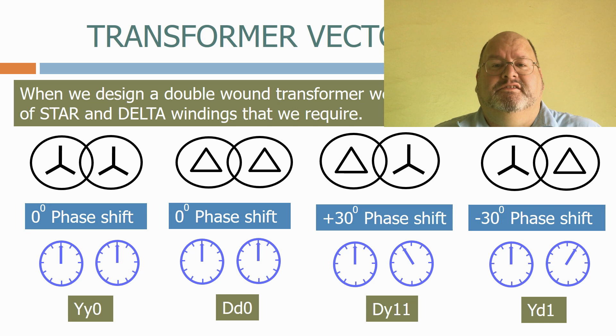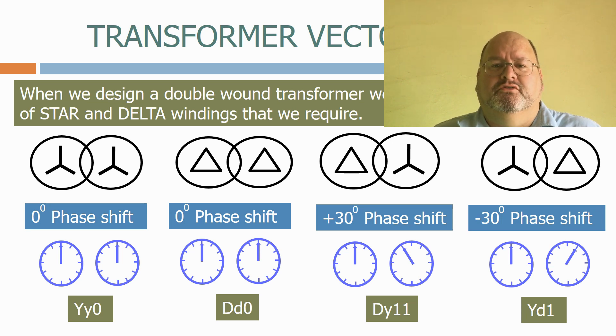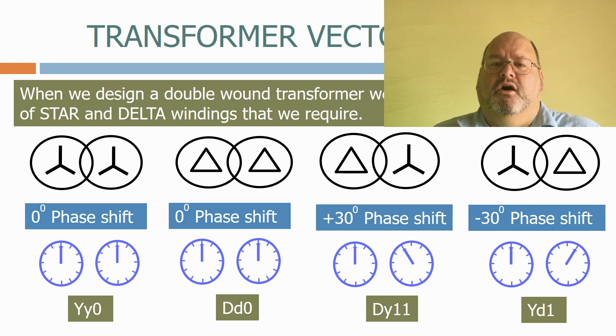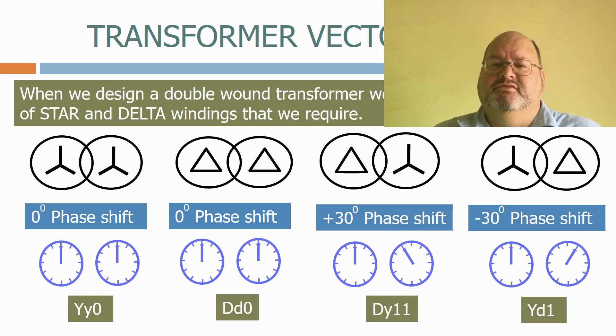Designers take this phase shift into account when they design the electrical network, to ensure that the voltages that appear at each voltage level in their network always have the same phase angle. Trying to join two networks with a 30-degrees phase shift would be blocked by the synchronizing relay on the circuit breaker.